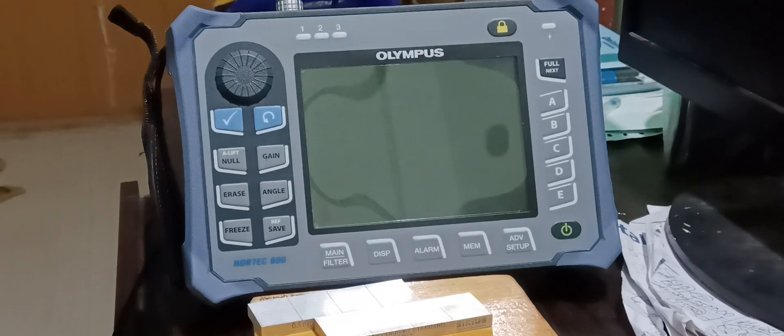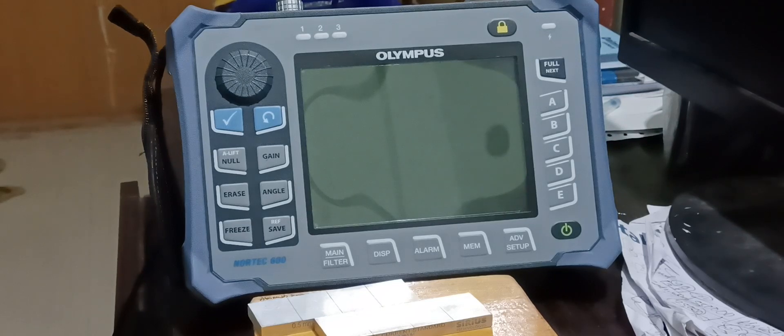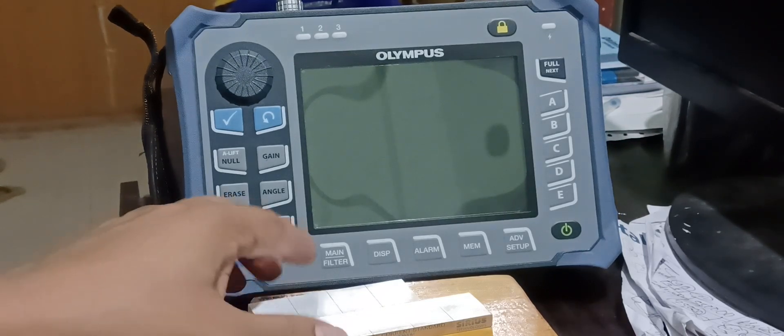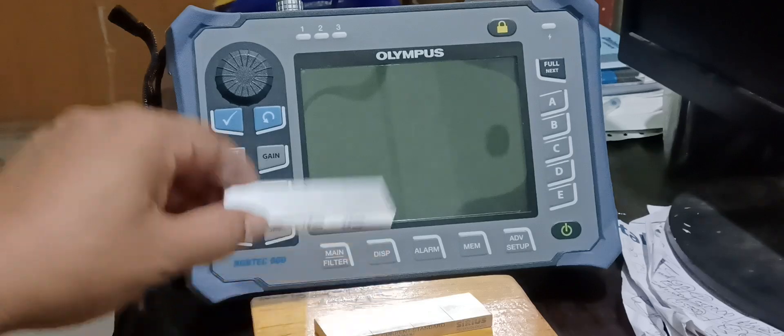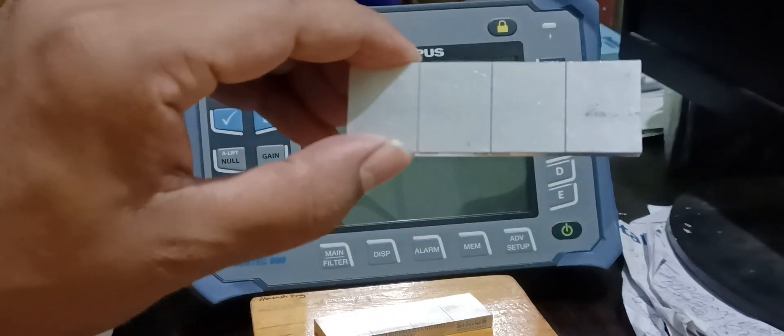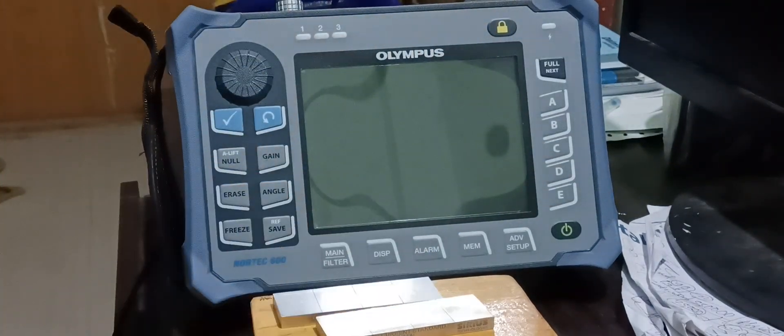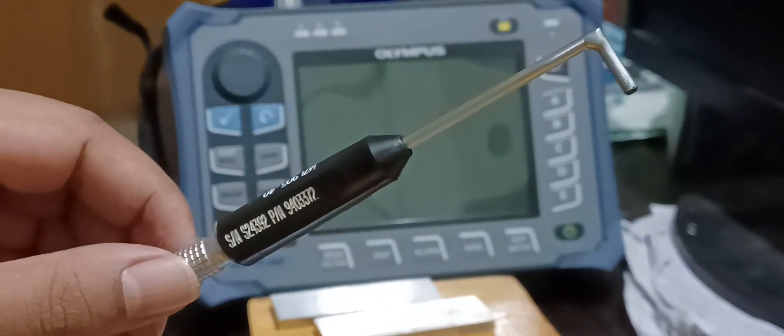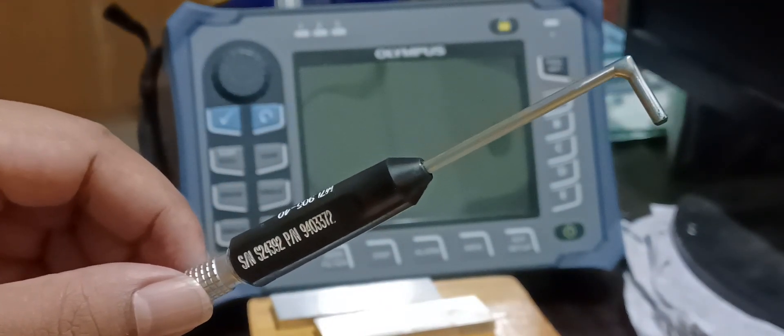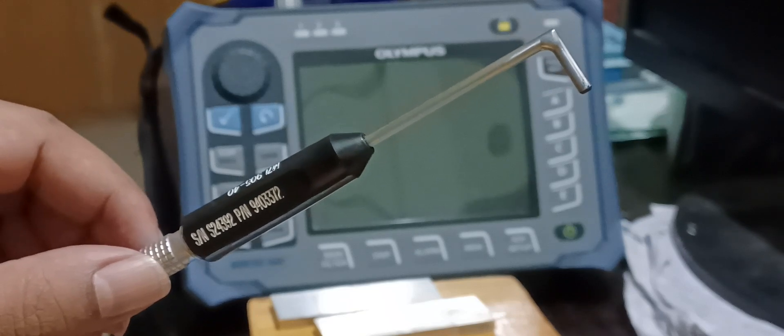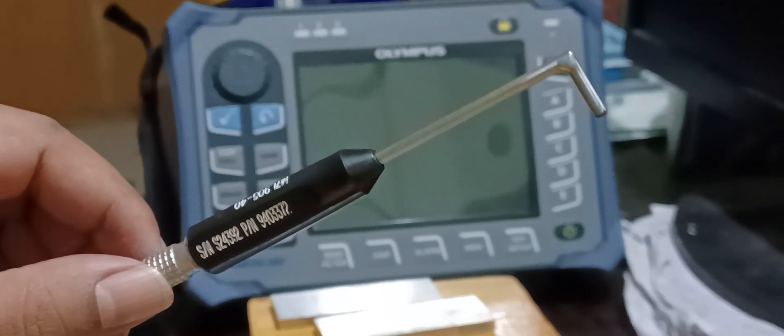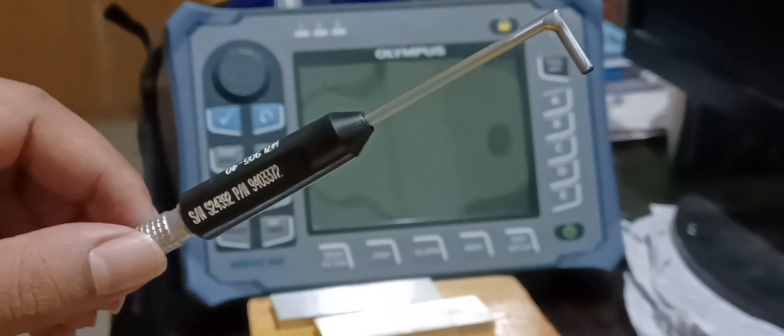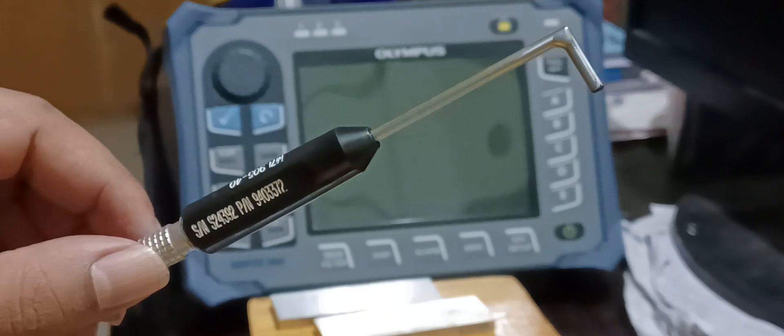In this video we will learn how to properly calibrate an eddy current equipment with available surface crack standards and with a 90 degree or L type bend probe. This is also called a surface probe and it is having an absolute coil arrangement.